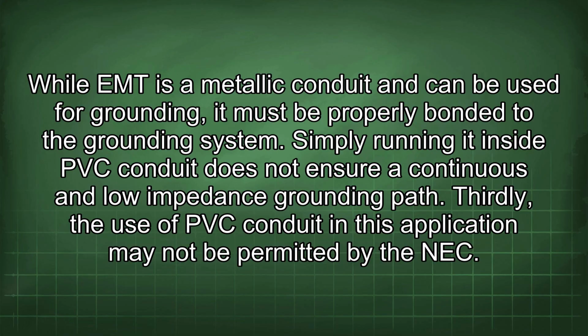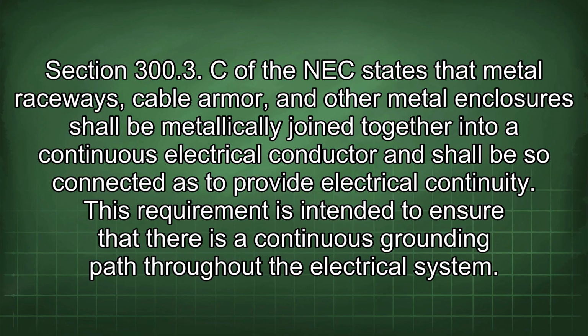Thirdly, the use of PVC conduit in this application may not be permitted by the NEC. Section 300.3(C) of the NEC states that metal raceways, cable armor, and other metal enclosures shall be metallically joined together into a continuous electrical conductor and shall be so connected as to provide electrical continuity. This requirement is intended to ensure that there is a continuous grounding path throughout the electrical system.